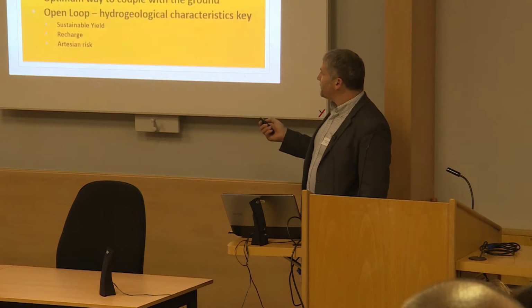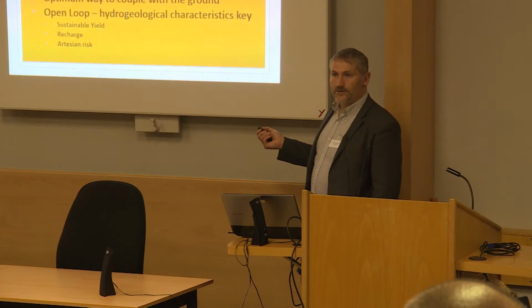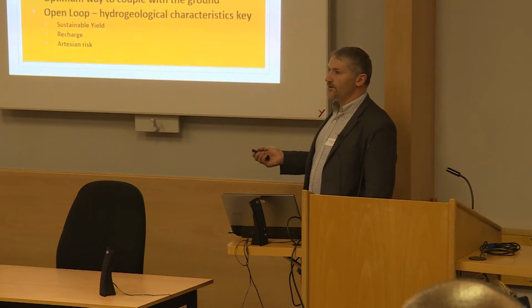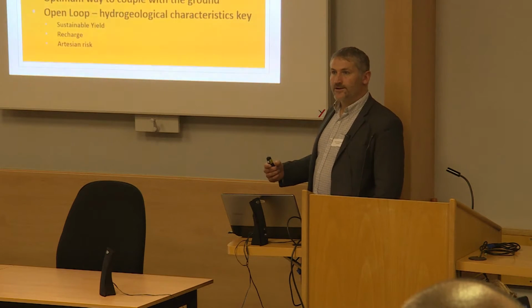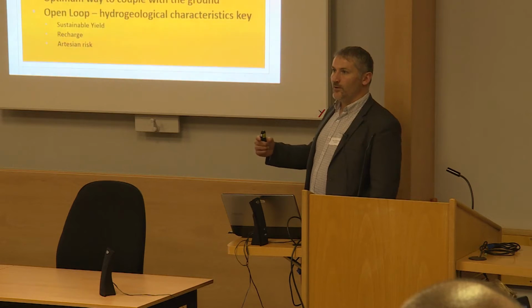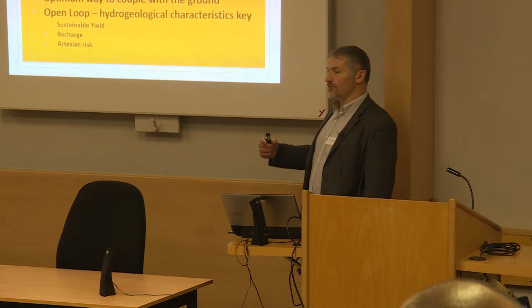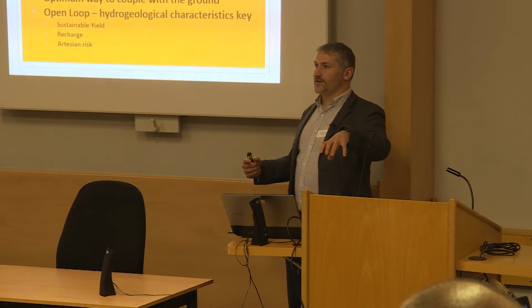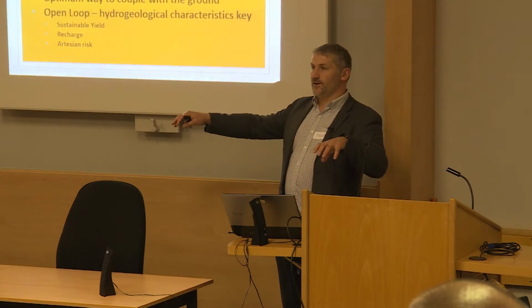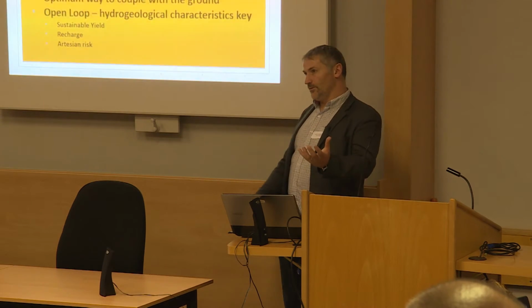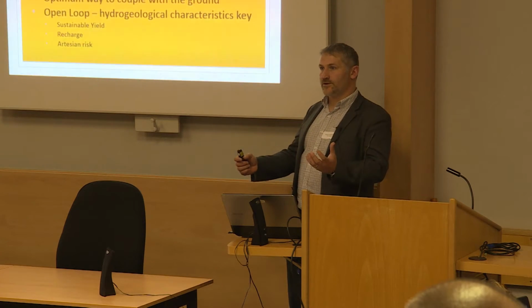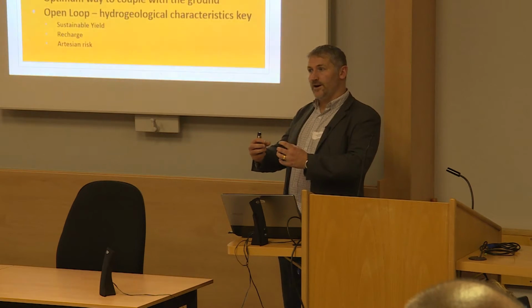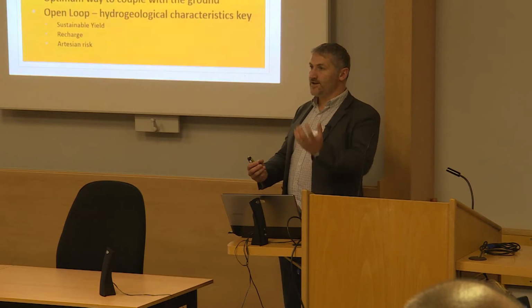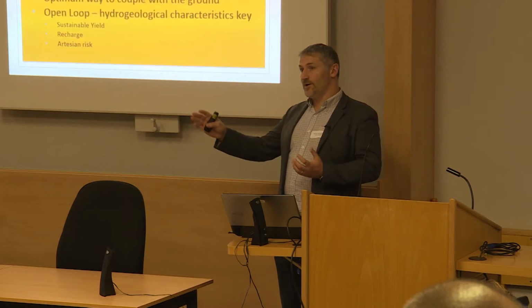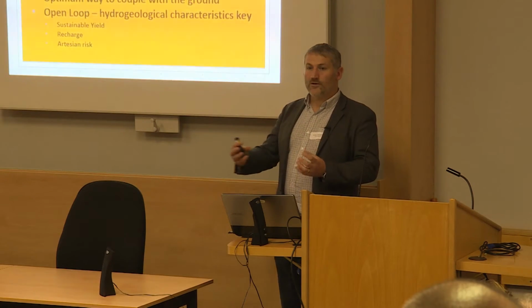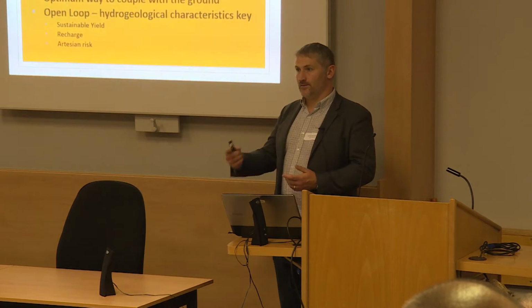With all this information, what we're trying to find is the optimum way to couple with the ground. Typically for very large heating-only projects, when you go beyond a few hundred kilowatts, it's probably better to look at open loop systems where you're drilling groundwater wells, abstracting from one side of a site, and discharging a few hundred meters away on the other side. That way you're getting nice, fresh, relatively warm 10, 12 degree water coming to you all the time. If you have it too close together, if your site's very small, you'll get thermal interaction between the wells. So the water you've taken out at 10 degrees, dropped it down to say 5 degrees, as it comes back at you it won't have warmed up in time, and you get what's called thermal breakthrough, and your system will degrade over time.